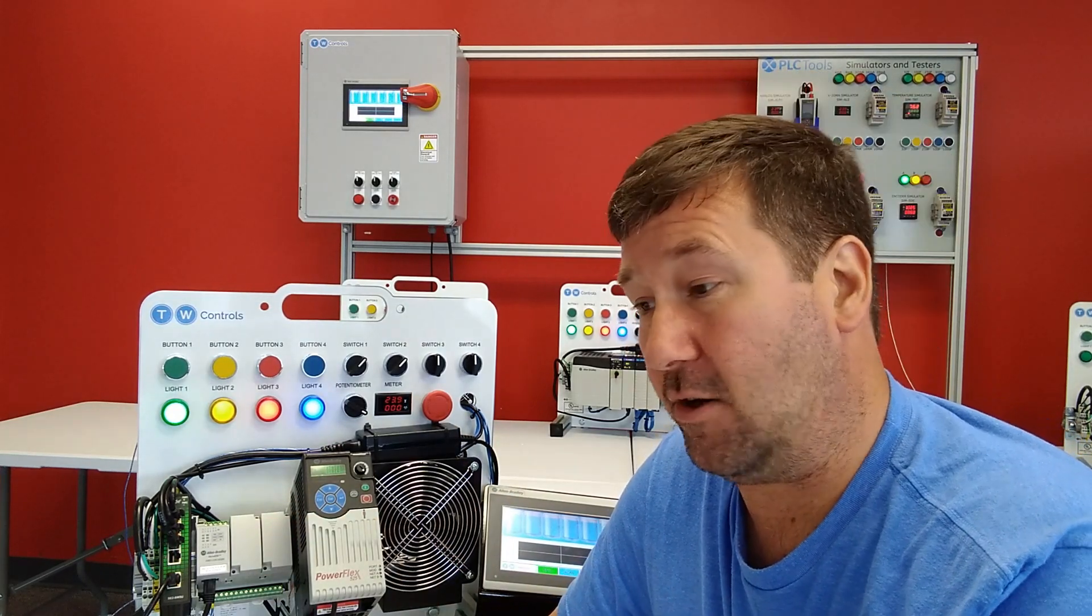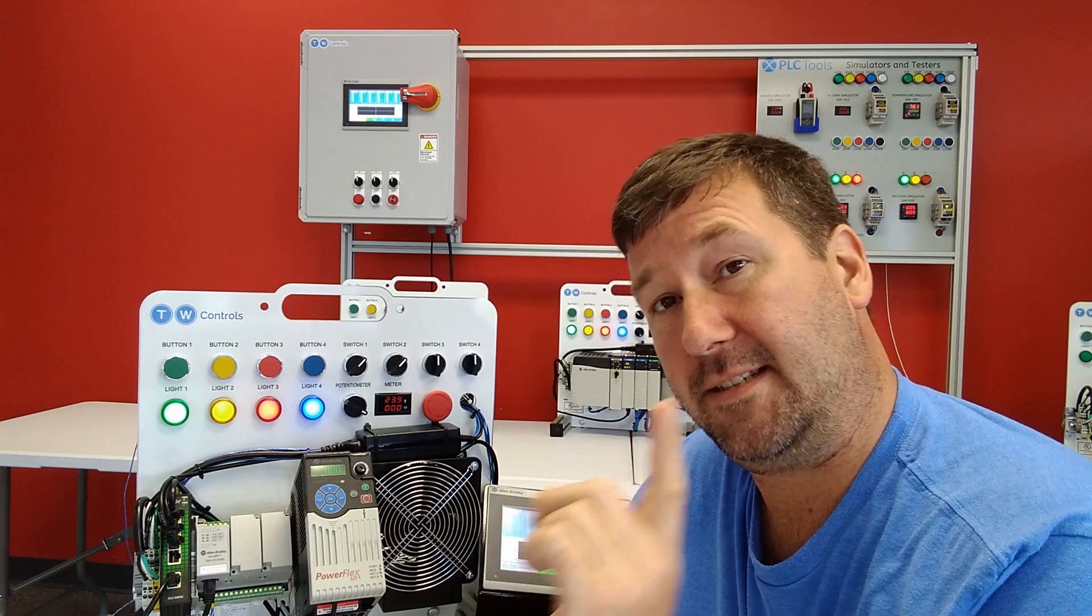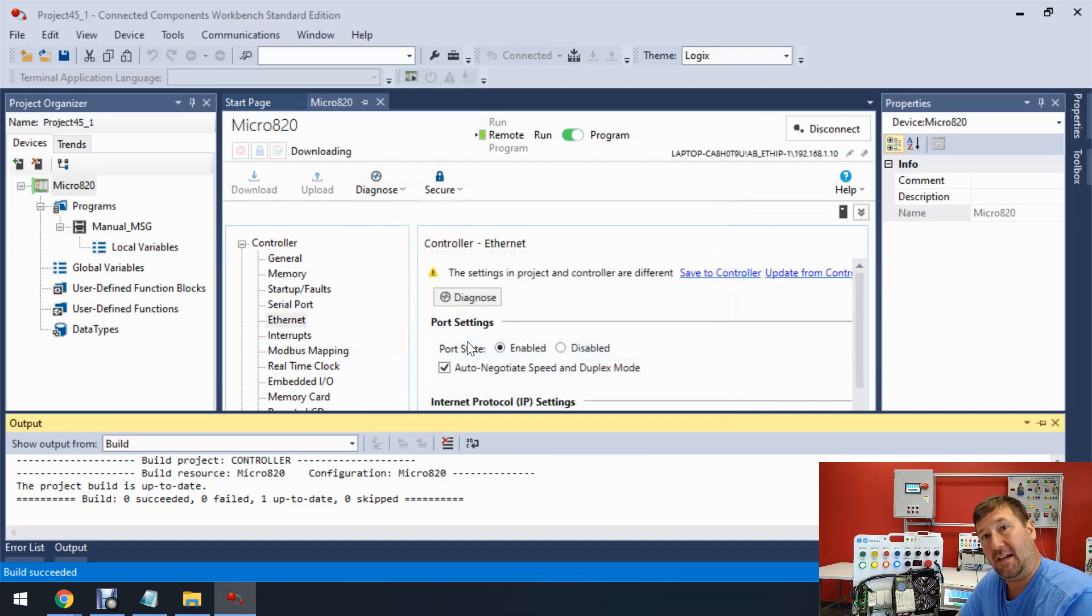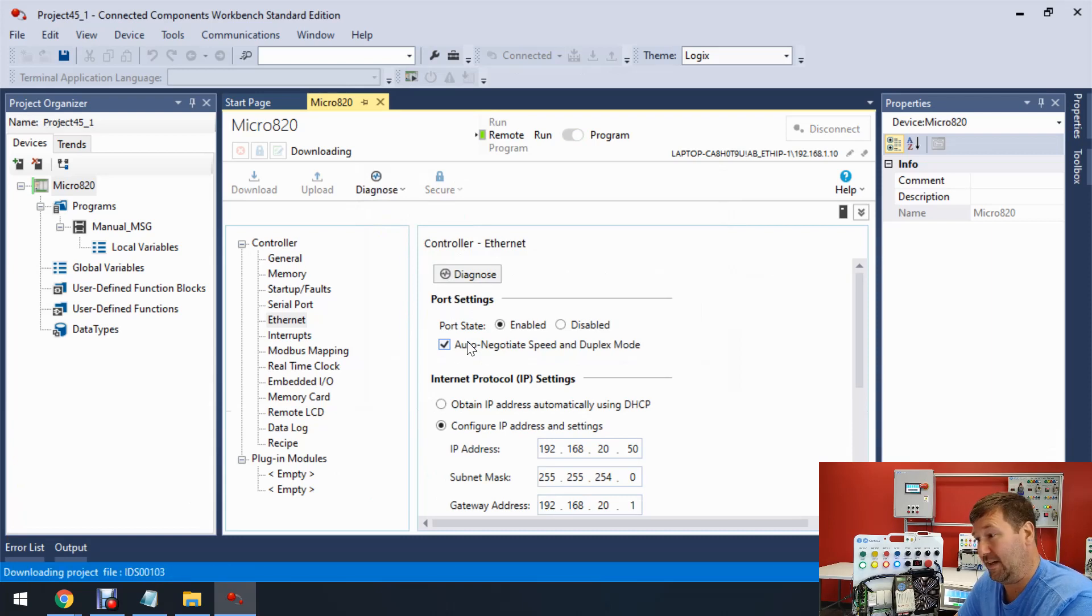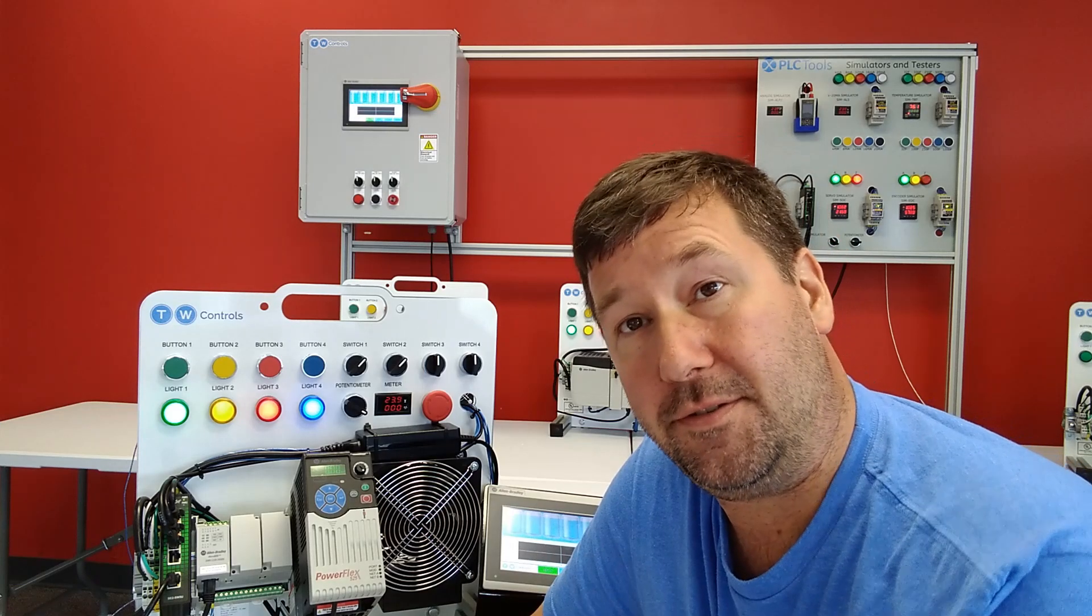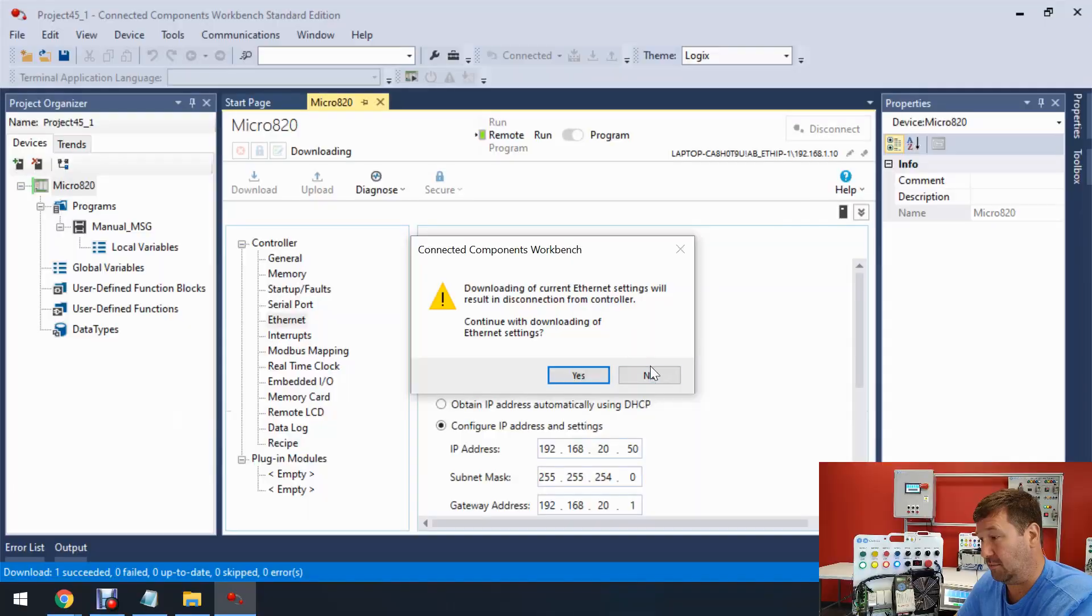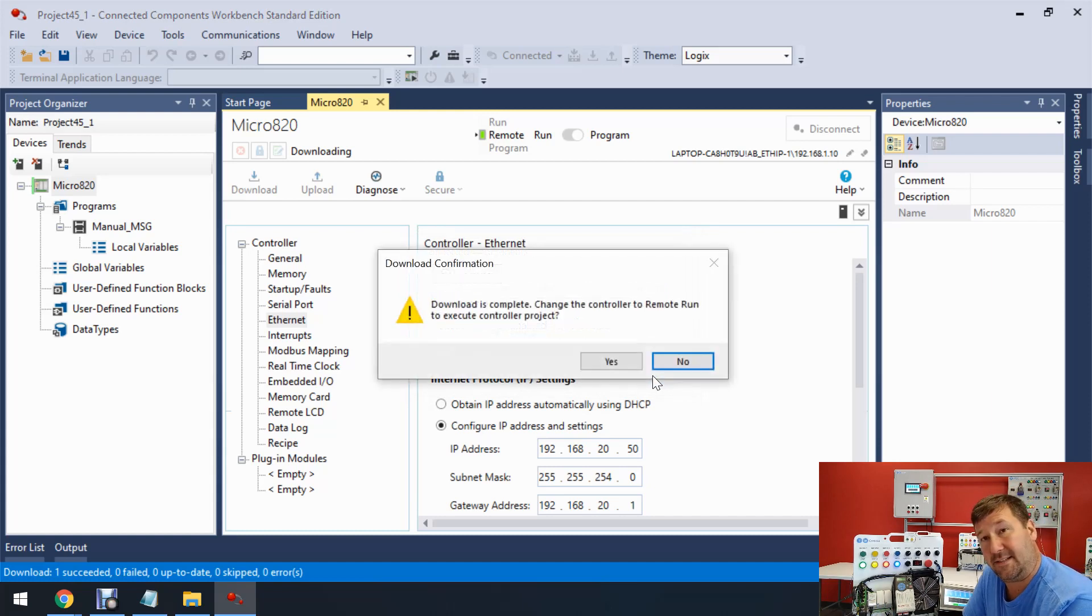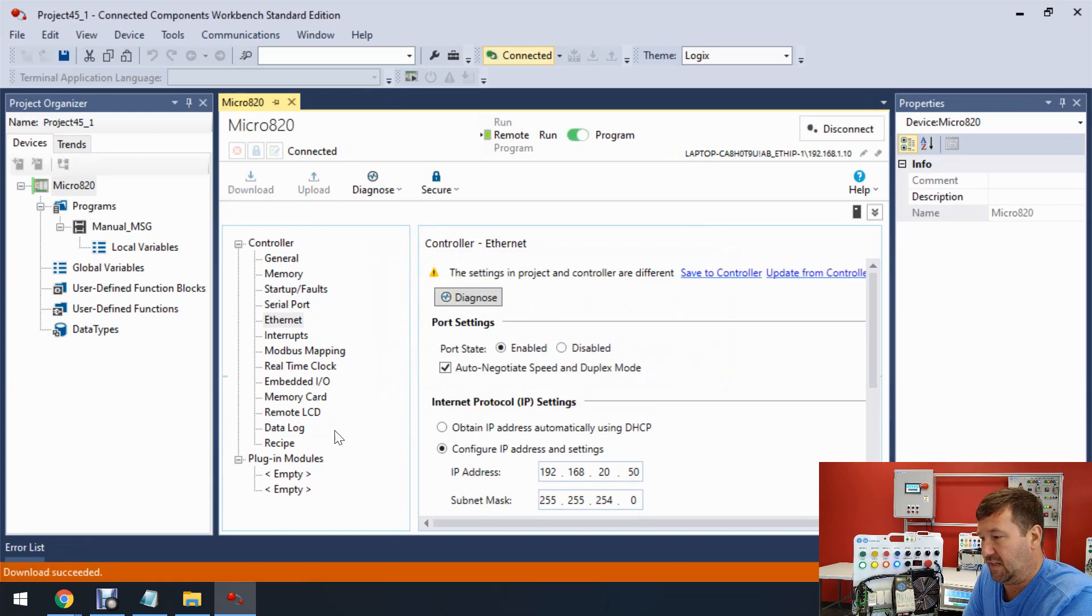And I almost slipped up and forgot about our Ethernet configuration. Actually, before we fix our Ethernet configuration here, let's go ahead and download this. Take it one step at a time. Because I just want you to see this warning and understand it. Because I get a lot of calls from people that have downloaded a program and all of a sudden they can't connect to their PLC. And it's almost always this Ethernet configuration. So right here, it gets this prompt. Downloading the current Ethernet settings will result in disconnection from controller. Continue with downloading of Ethernet settings. If you see that, you need to make sure that you have the Ethernet settings correct. And I don't have them correct. So I'm going to say no here. It downloaded the program. I'm going to click no. And it's actually going to let us go ahead and go with it. It could go ahead and go to run mode. We're not going to do that because I want to fix this. So let's click no.